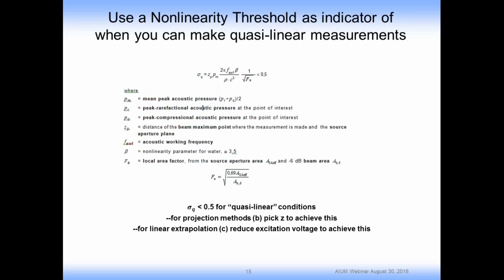I'll briefly also mention how you can be assured that you're in the linear regime. This is a somewhat complicated formula, but it's directly from the standards. Basically, if you measure certain parameters such as the pressure, the frequency, the distance, and some of the focal properties of your source, you can estimate the degree of nonlinearity. And currently, the standards request this sigma parameter, which is the nonlinearity, to be less than 0.5.